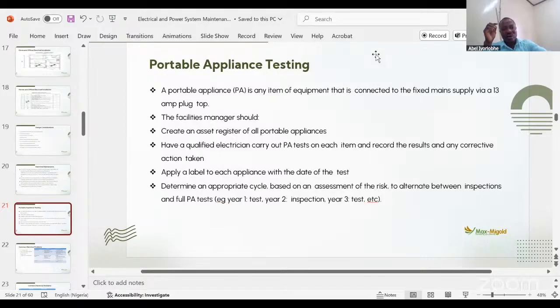So you have a logbook that shows all the tests you have carried out, like on the LT system. You test every interval, like taking readings on your generator, and you write them down. If you are deviating from the normal, you know something is wrong. Like I told you, a certain frequency must be observed, between 48 and 52.